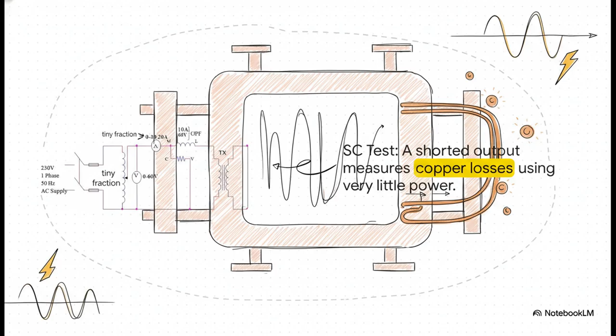To measure this without blowing anything up, we do the short circuit test. Here's where it gets clever. We intentionally create a short on the output, and then we apply just a tiny fraction of the rated voltage to the input, just enough to drive the full rated current through those windings. This brilliantly mimics the full load current condition without needing massive amounts of power, letting us measure the copper losses precisely.